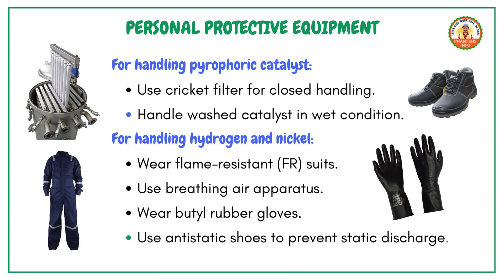Personal protective equipment (PPE). For handling the pyrophoric catalyst: use a cricket filter for closed handling; handle washed catalyst in wet condition. For handling hydrogen and nickel: wear flame-resistant (FR) suits; use breathing air apparatus; wear butyl rubber gloves; use anti-static shoes to prevent static discharge.